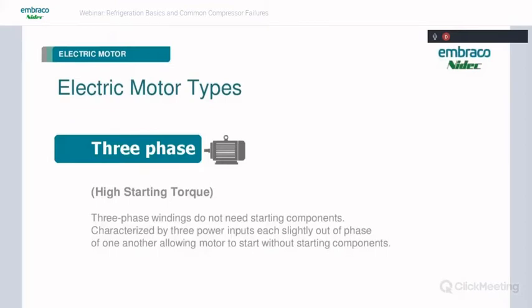And then above 1.5 horsepower, you'll start to see some 3-phase motors, and especially in air conditioning, where you get above a 3-ton or a 3 horsepower compressor, you're going to see 3-phase. And these are characterized by 3 leads of power, each slightly out of phase from each other. So this alleviates the need for starting components, because the power is slightly out of phase, and that gives it the rotational force to get it going without start components other than a relay. You just need a large heavy duty, not a relay, but a contactor, large heavy duty switch just to turn it on and off. And then the 3-phase power does the rest. These are high starting torque and high running torque by design. So of course you're going to see these on a very large 3+ horsepower compressor motors. Like I say, a lot of your commercial air conditioning technicians are more familiar with this. They're fairly simple as far as components go.